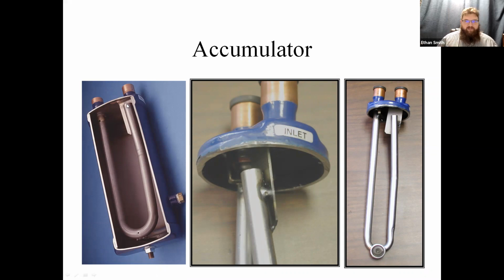Unfortunately, anytime we're pumping refrigerant, we are pumping oil out of the compressor. So we have to have a provision to bring that oil back. So I've got this little bleed hole down here. It's usually got a screen of some sort on it, like you see on the right down here. Occasionally that bleed hole or that screen will get plugged up. Usually this is due to people brazing without nitrogen, or having dirty line sets, or pushing their line sets through sheetrock walls and getting debris and things like that come in. They accumulate in the accumulator and will cause that little tube to plug up.